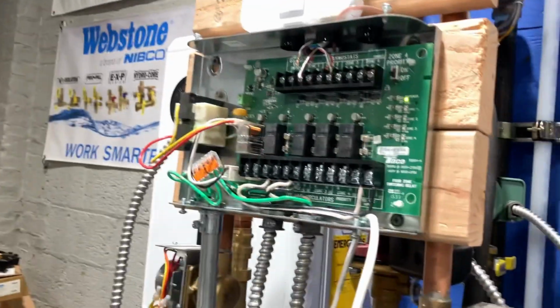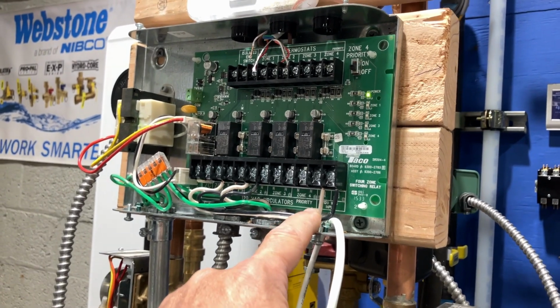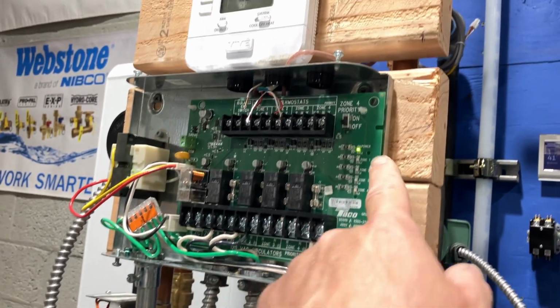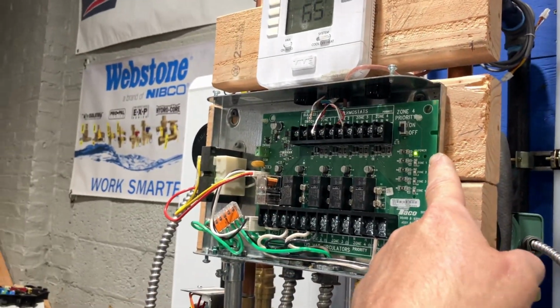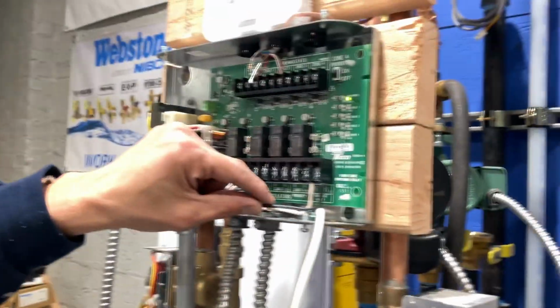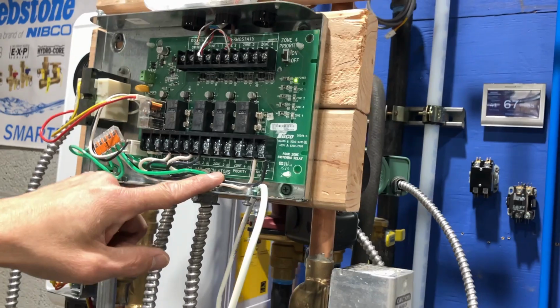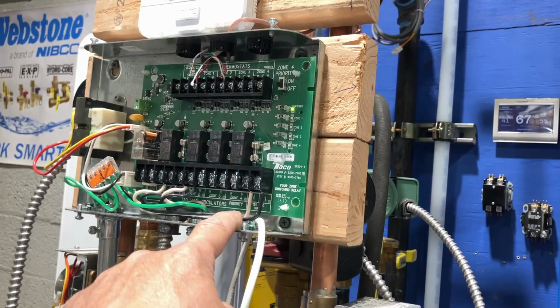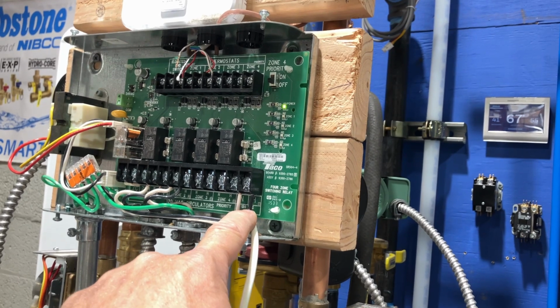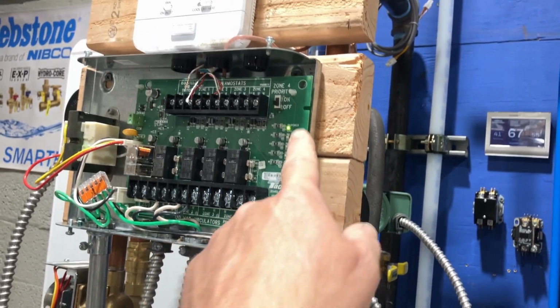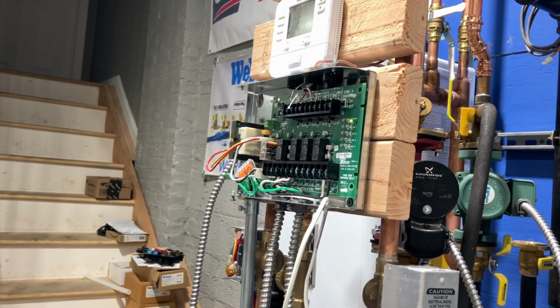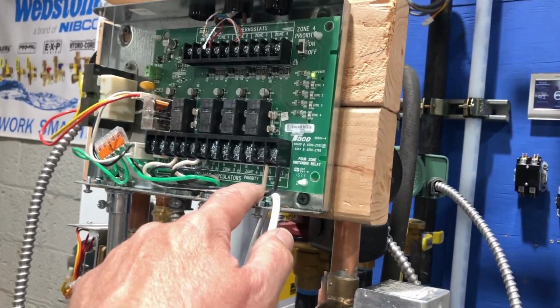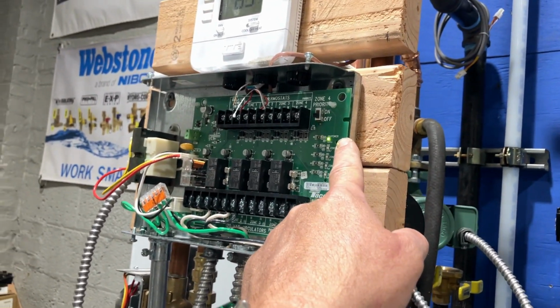Do you agree? If there's incoming power to the 110 volt AC input, that light should be on. Do you agree? Yeah. Okay. Is that your final answer? Be careful, that's live voltage. No, let's pay very, very close attention. If there's line voltage going to the terminals for the input of voltage AC, that green light should be on, correct? For both terminals, yes. Hot and neutral. If we have line voltage coming in here, that green light is going to be on. Correct. Okay. Should be on is the key word, okay?